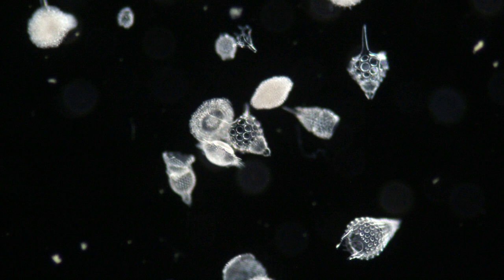So how does this now work? When you look at one of those dark field filters you're going to see that they have essentially two regions: the central patch stop which blocks out the main microscope light, and the peripheral annulus, this bright part that allows light to go through.